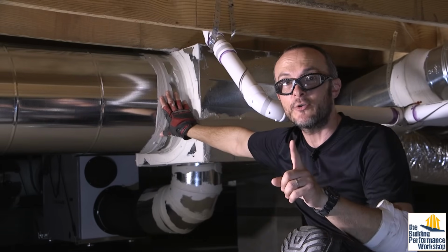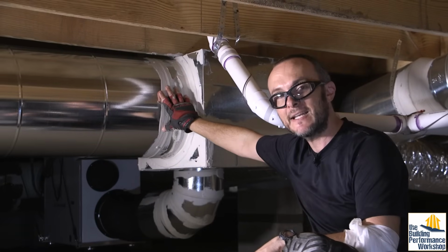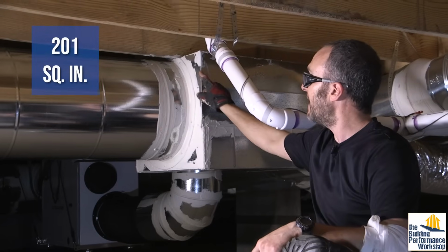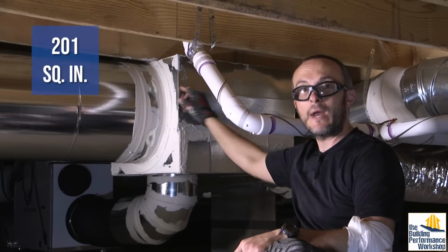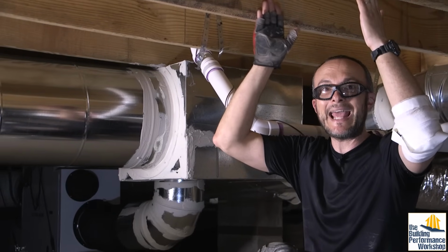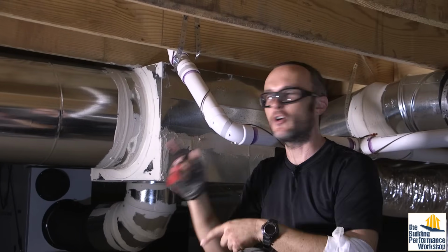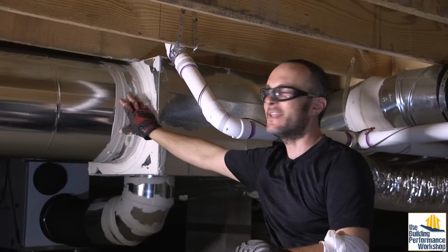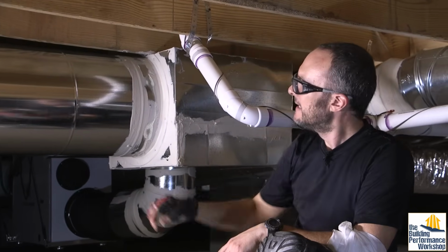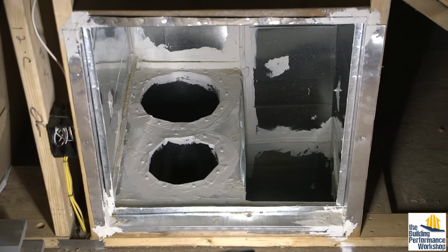By the way, you want to make sure to always calculate how big all of these openings need to be relative to each other. So it's 16-inch round. I know how many square inches of opening that is. And then I found out how much of a rectangle I need if I'm trying to fit down between these two floor joists, which is 14.5 inches wide. What is the length I need in order to make sure that I'm not restricting, that this is not bigger than what it's coming through first. And so on the other side of this, we've got 2 rounds, one 8-inch and one 10-inch round.